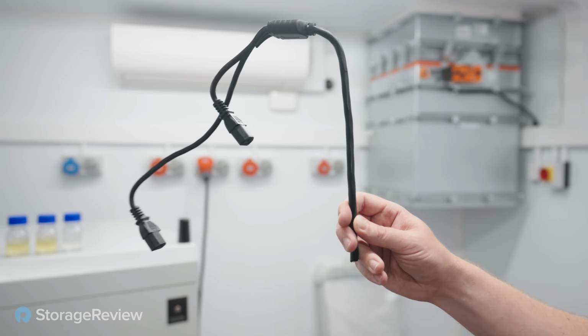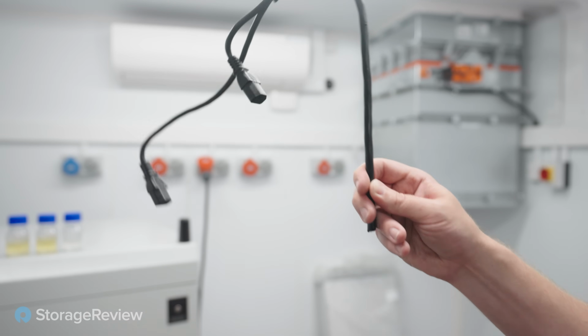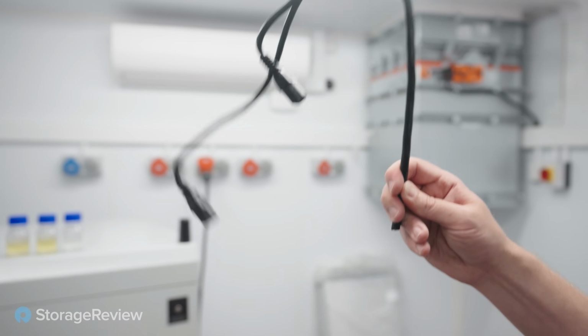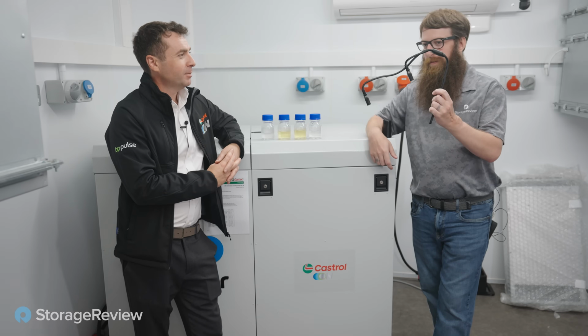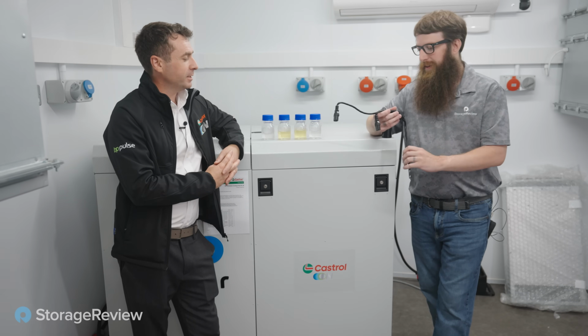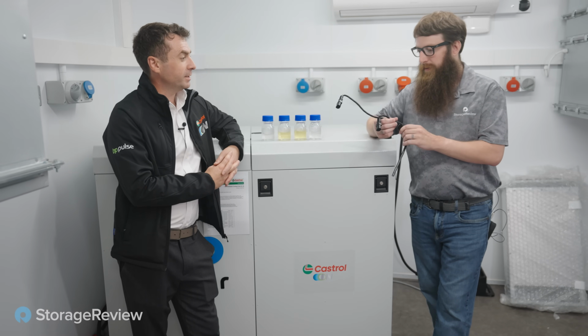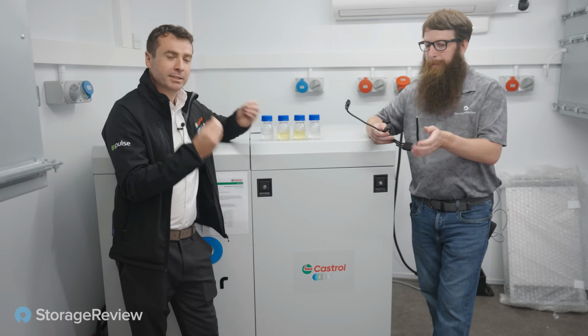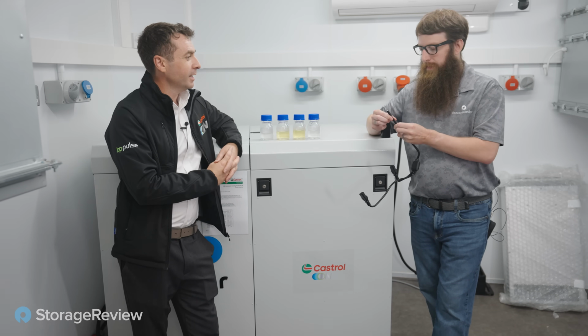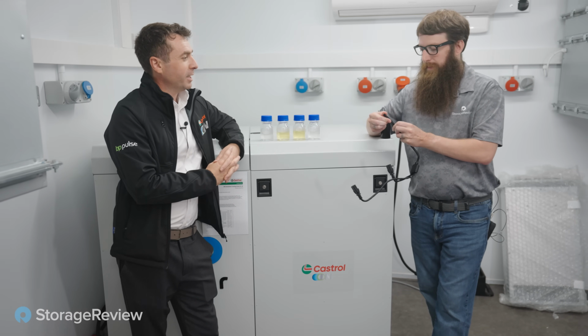Material compatibility is really important - understanding what works, what doesn't, what materials you can use and what to stay away from. What's in your hand is a power supply with PVC sheathing. Typically with single phase immersion fluids, PVC goes very brittle and stiff as the plasticizers are removed from the material. Not a problem until you need to use it.